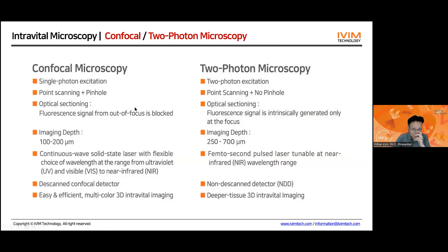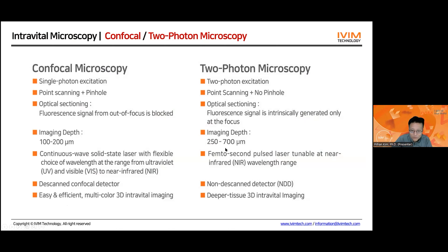Comparing confocal and two-photon microscopy, they are complementary to each other. Confocal microscopy is easy to use and very efficient in fluorescence imaging, and it's very easy to do multicolor imaging. For two-photon microscopy, imaging depth can be extended further — up to 500 to 700 micrometers — so for deeper tissue imaging, two-photon microscopy has an advantage.